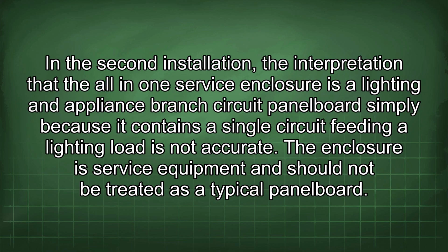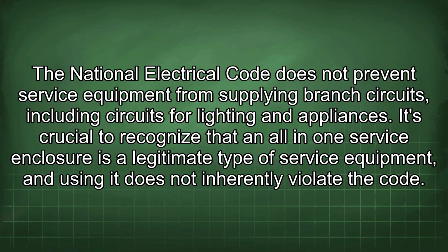In the second installation, the interpretation that the all-in-one service enclosure is a lighting and appliance branch circuit panel board simply because it contains a single circuit feeding a lighting load is not accurate. The enclosure is service equipment and should not be treated as a typical panel board. The National Electrical Code does not prevent service equipment from supplying branch circuits, including circuits for lighting and appliances. It's crucial to recognize that an all-in-one service enclosure is a legitimate type of service equipment, and using it does not inherently violate the code.